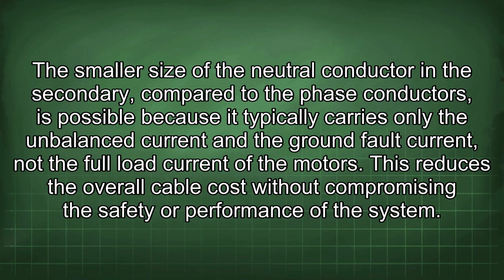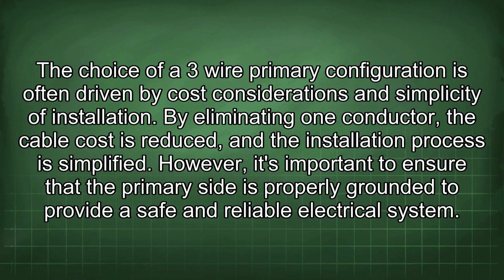The smaller size of the neutral conductor in the secondary, compared to the phase conductors, is possible because it typically carries only the imbalanced current and the ground fault current, not the full load current of the motors. This reduces the overall cable cost without compromising the safety or performance of the system. The choice of a 3-wire primary configuration is often driven by cost considerations and simplicity of installation. By eliminating one conductor, the cable cost is reduced, and the installation process is simplified. However, it's important to ensure that the primary side is properly grounded to provide a safe and reliable electrical system.